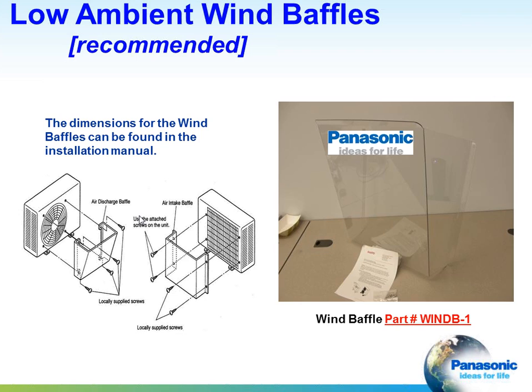All right, low ambient wind baffles. These are always recommended whether you have a heat pump or cooling only, for a couple of different reasons. Heat pumps will go into defrost mode periodically if frost builds up, and that's going to happen with heat pumps in this area. As they're pulling heat out of the air, they cool the air, and you're going to have some frost build up on the outdoor coils. The way that they defrost with this equipment is the equipment turns off, and due to pressure differential, some of the hotter gas comes back through the discharge line, and that will assist in defrosting the coils.